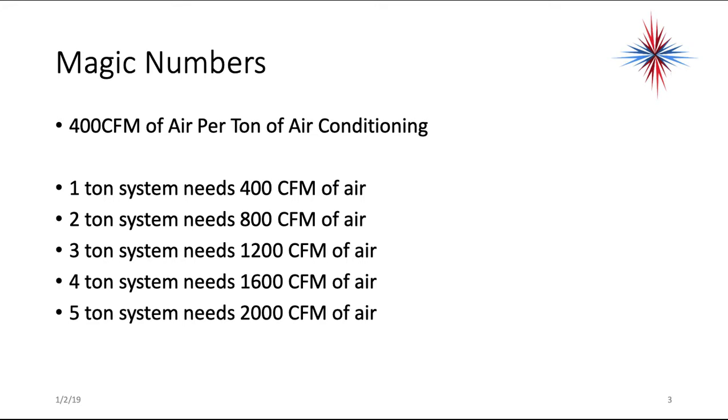Now you're going to run across 1.5-ton systems. They would need 600, 2.5 would need 1000, 3.5 would need 1400, and so on. You can multiply up from there. But those are the key. This is a very important number to remember.